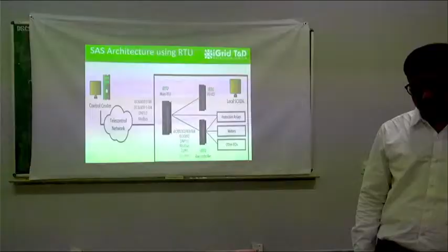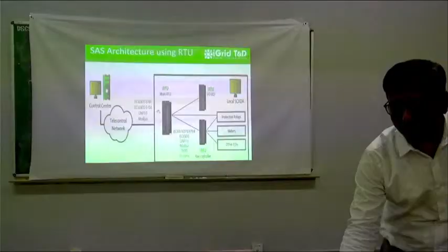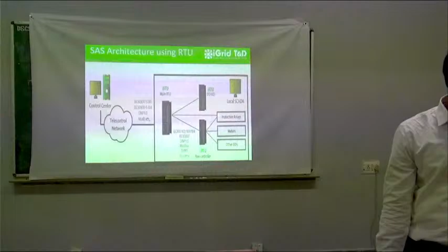So this is just another example that we have given. This is the main RTU, and there are other sub RTUs. Again, it's just an example: we can connect to multiple RTUs, which in turn are connected to the main RTU. You have another RTU which is connected to the protection relays, meters and other IEDs, and then you can see the data in local SCADA. My gateway has the capability to send the data in IEC 101, 104, DNP3 or Modbus. Okay.